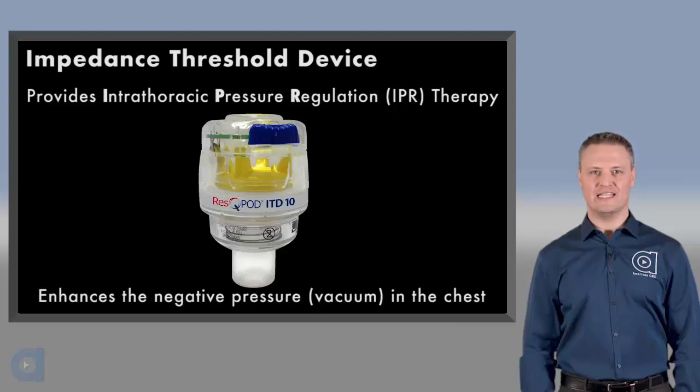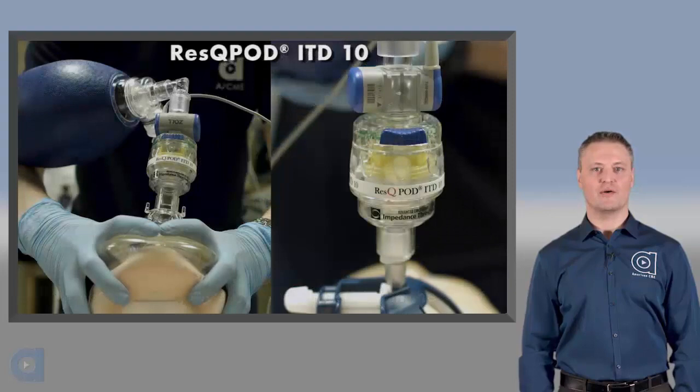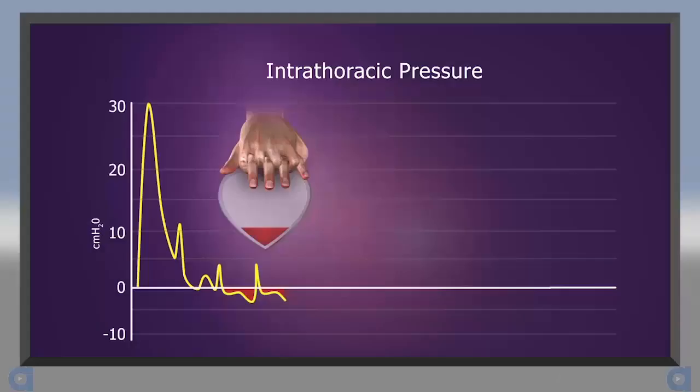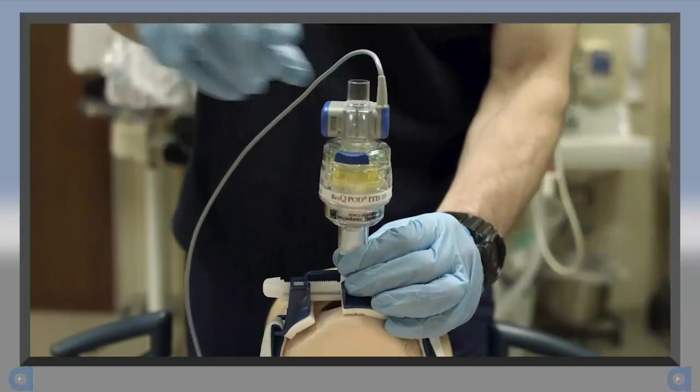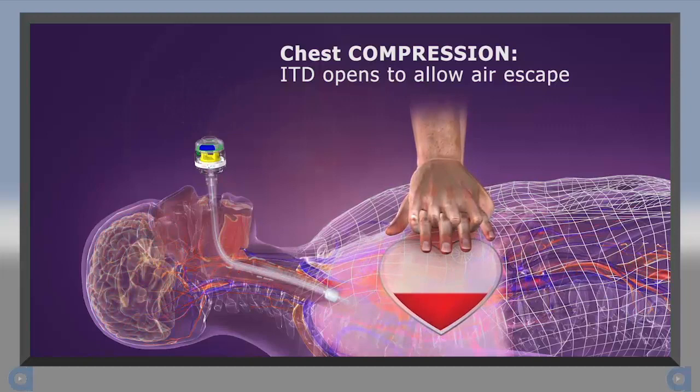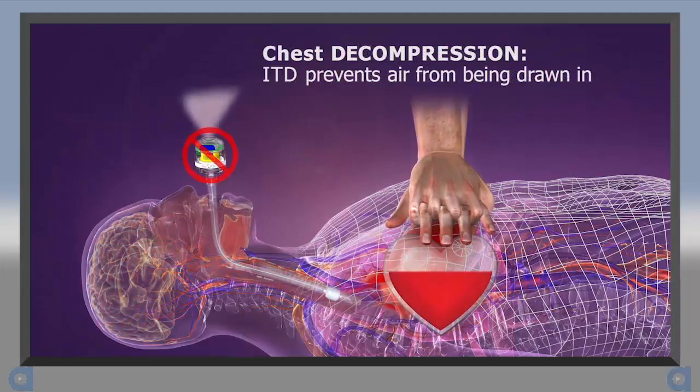The ResQPOD ITD-10 is an impedance threshold device, or ITD, that is used to provide IPR therapy during cardiac arrest. Recall that during CPR, positive pressure helps to circulate blood forward, while negative pressure — or a vacuum — helps to refill the heart. An ITD fits into the airway circuit on a face mask or advanced airway. During chest compression, the ITD's valve opens and air is forced out of the lungs and through the ITD without resistance. But as the chest wall recoils, the ITD's valve closes and selectively prevents air from being drawn back in.